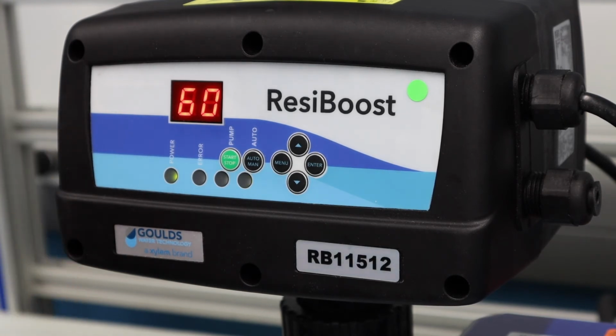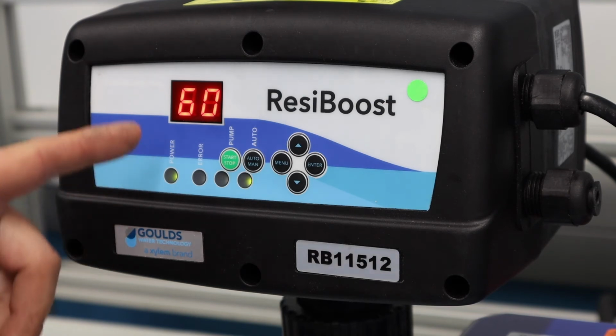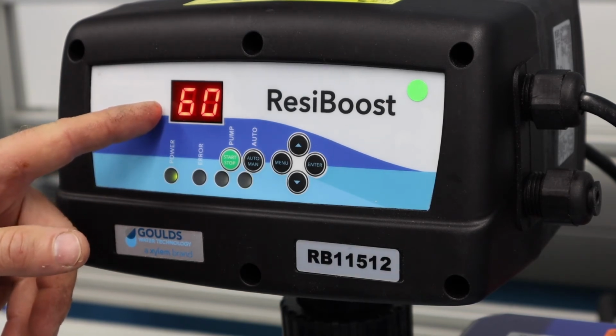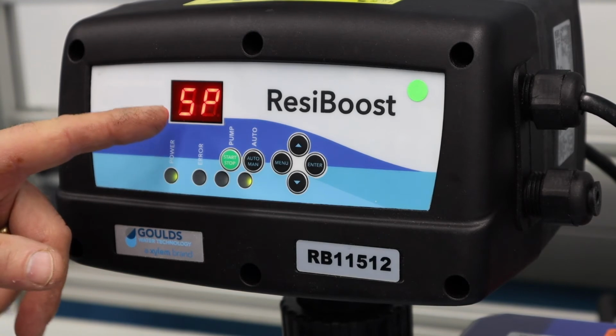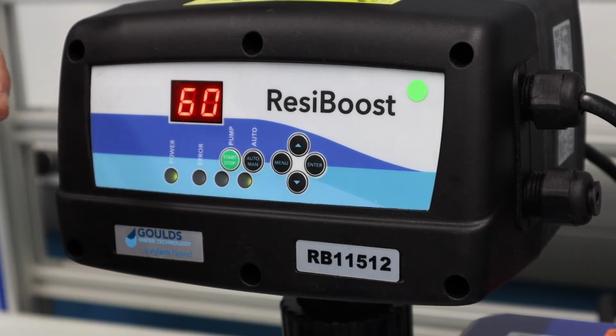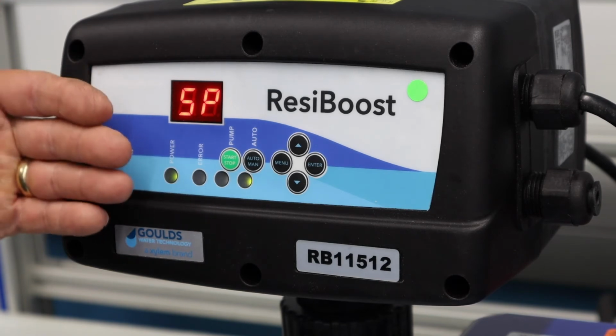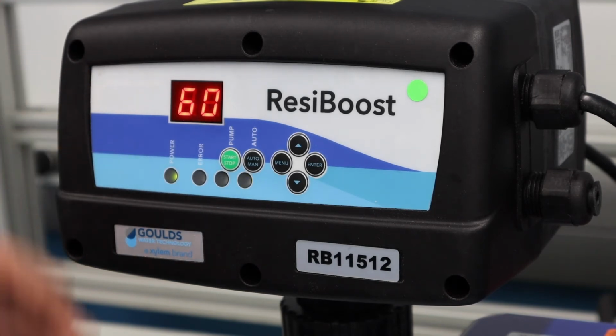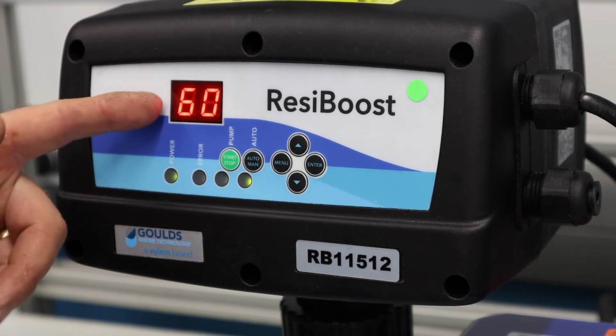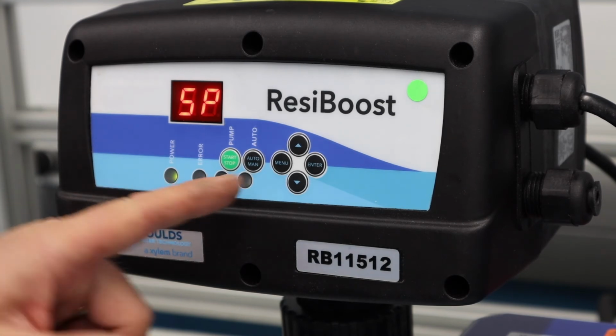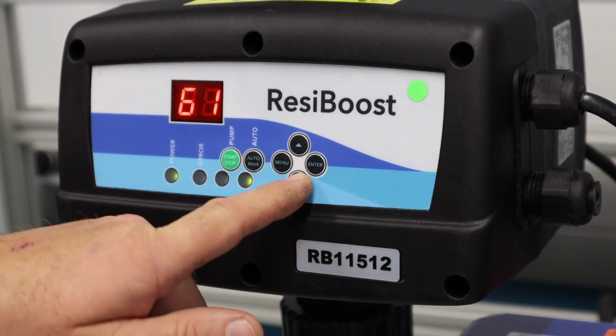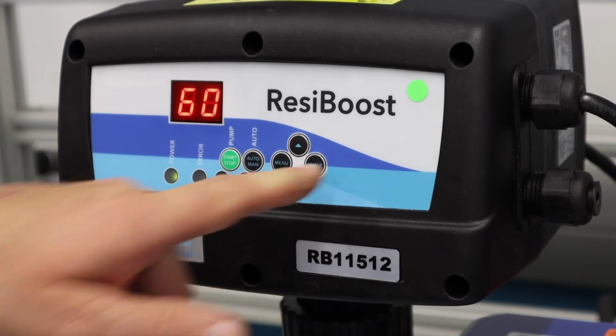Okay, set pressure is your system pressure. What do you want to maintain? And we can see the default is 60. Now in this case here, I'm going to use the default. I changed the pressure in my tank to 20 psi less than the set pressure, so 40. So I've got everything matched up, and 60 works good for me. But again, if you want to change that, you're going to hit your up and down arrows. Make sure you hit the enter button.